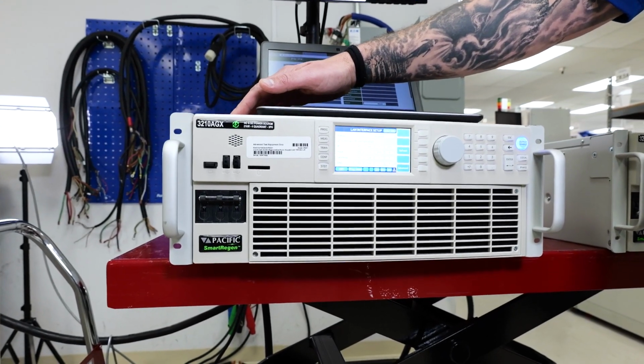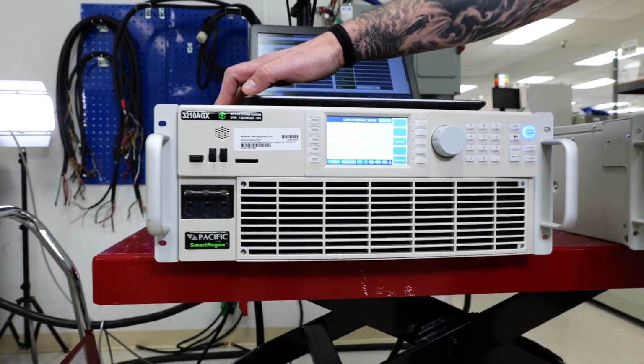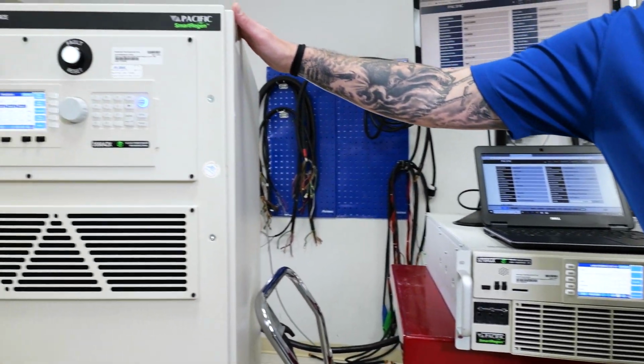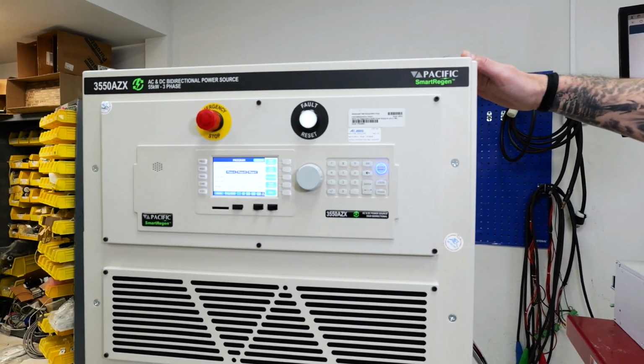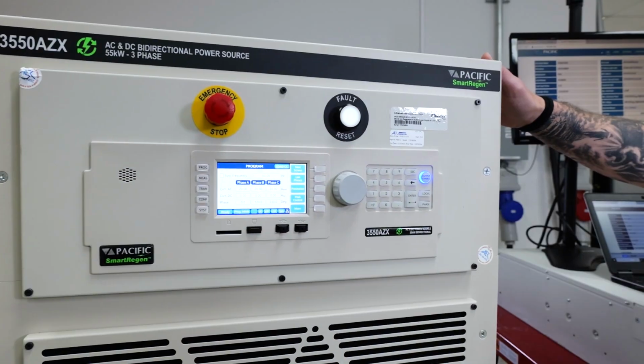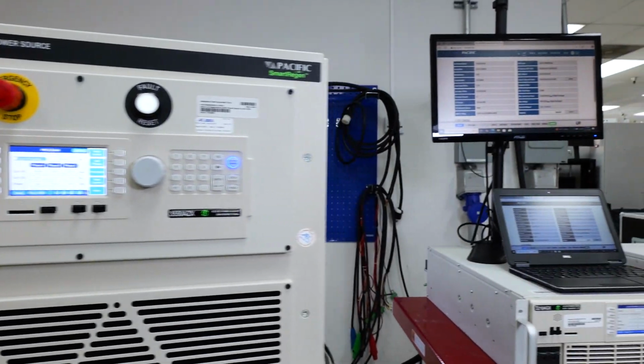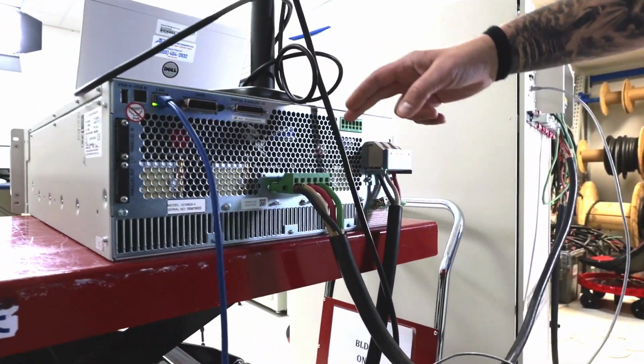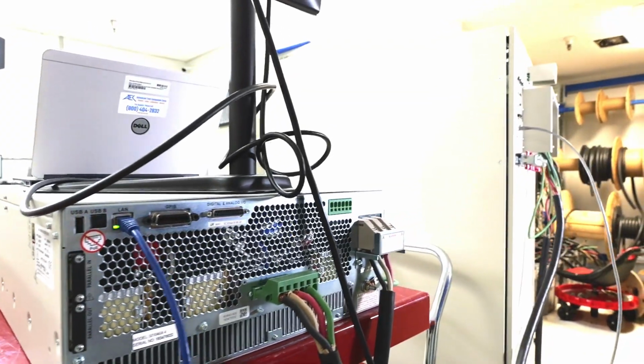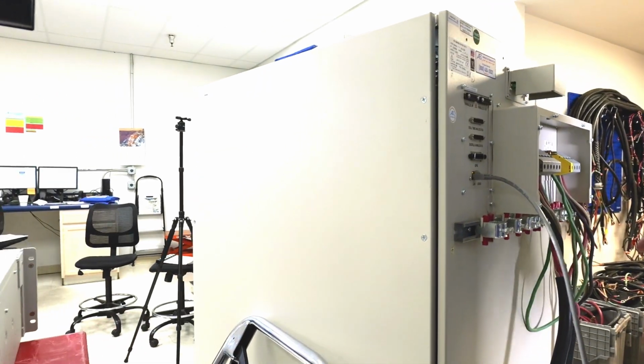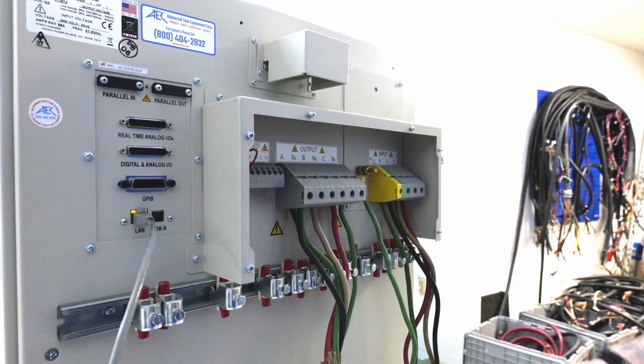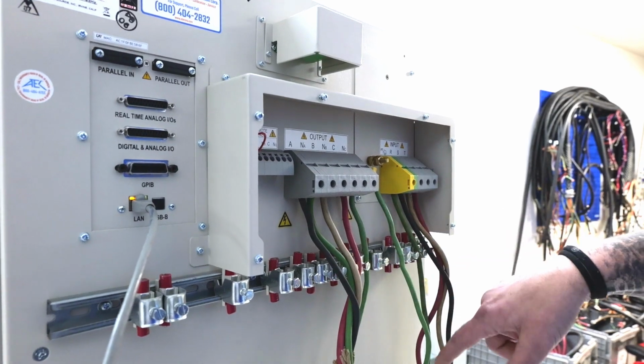This is going to be set up as a voltage source. We have it connected to the Pacific Power Source model 3550 AZX, which is going to be set up as our load. Let's take a look at the connections on the back. Here on the back of the AGX is the output connector, connected over to the output terminal block of our AZX, configured 3-phase to neutral, bonded to ground.